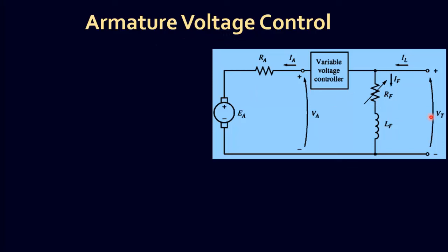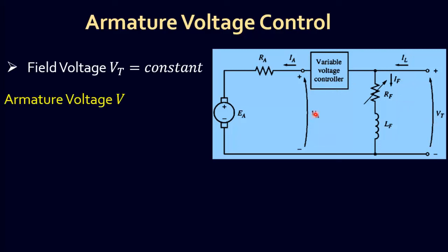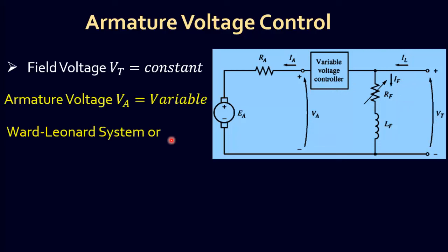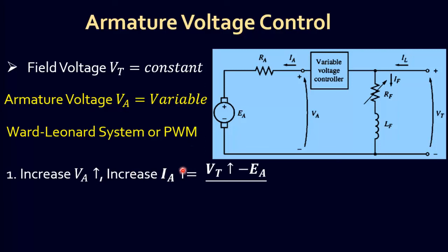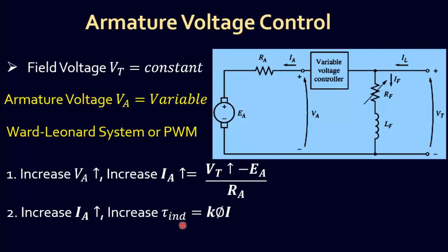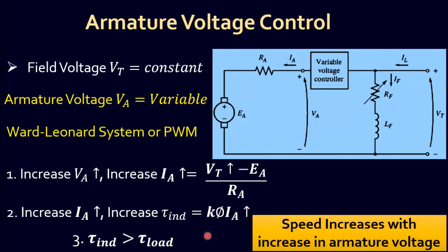As you can see in the diagram, the field voltage VT remains constant and only armature voltage VA is variable according to desired speed. The variable voltage can be achieved using the Ward-Leonard system or pulse width modulation (PWM). By increasing armature voltage VA, armature current IA is increased according to this relation. As the induced torque is greater than load torque, the motor speed is also increased.